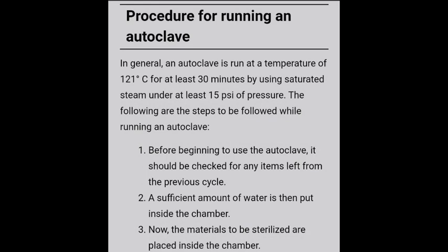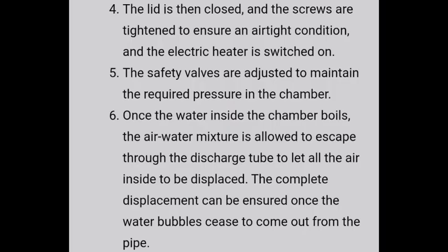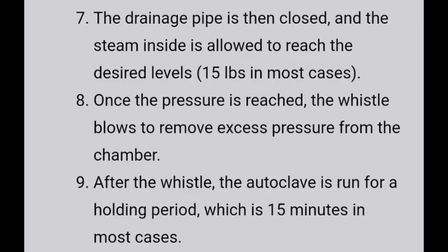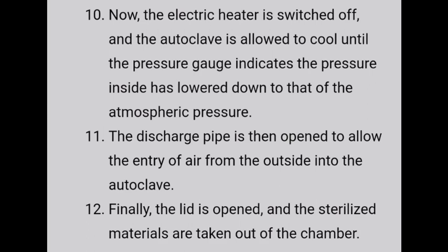In this video we are starting from the fact that we have already closed the lid of the autoclave and started it. After the lid is closed, we must make sure the temperature increases to 120 or 121 degrees Celsius, and then keep that for 15 to 20 minutes. Next we switch off the autoclave and allow it to cool until the pressure inside has lowered to that of the atmospheric pressure. Finally the lid is opened and the sterilized materials are taken out of the chamber.